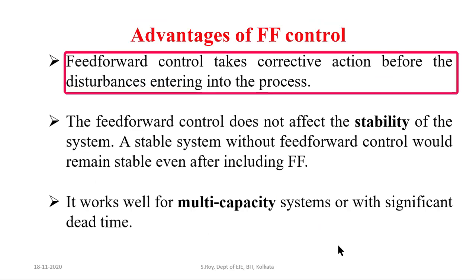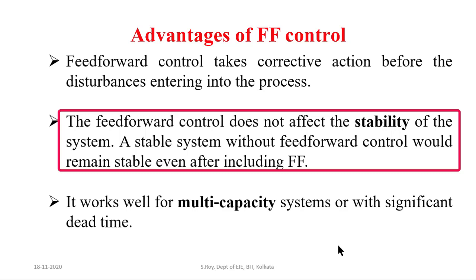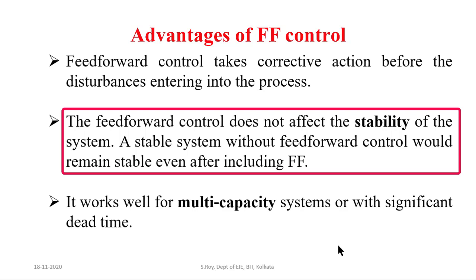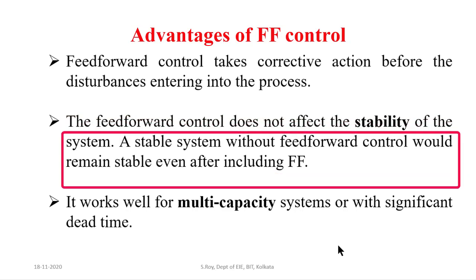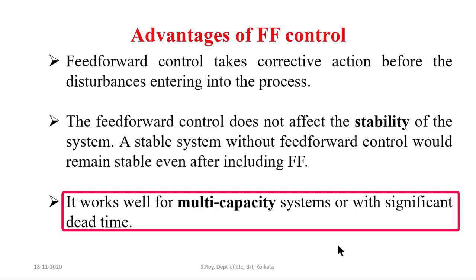Feedforward control is advantageous because it takes corrective action before disturbances enter and hamper the process, maintaining the control system perfectly. When combined with feedback or cascade control, the stability of the system is not changed — a previously stable system remains stable. Feedforward control also works well for multi-capacity systems and systems with high dead time.